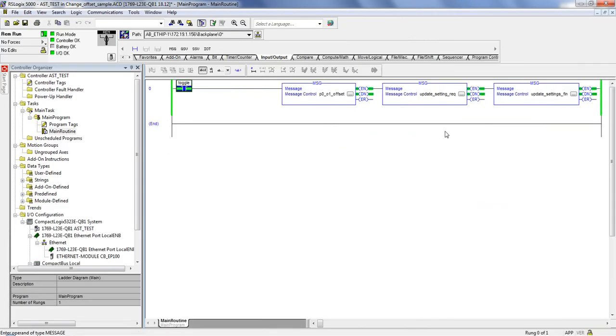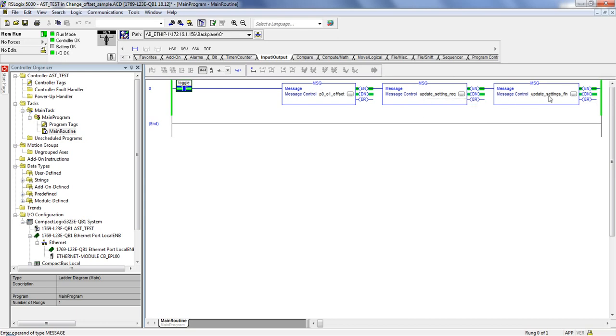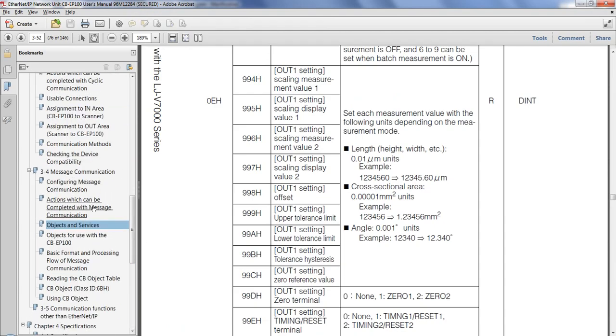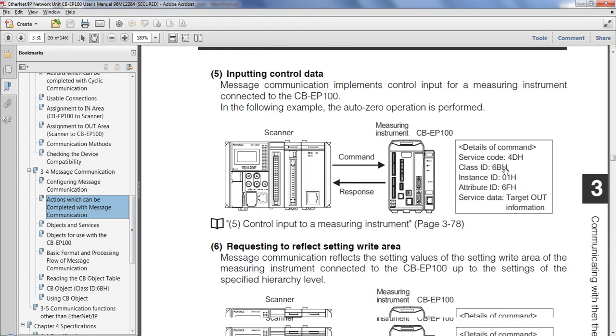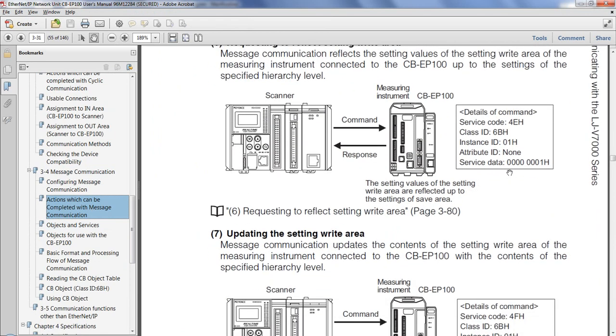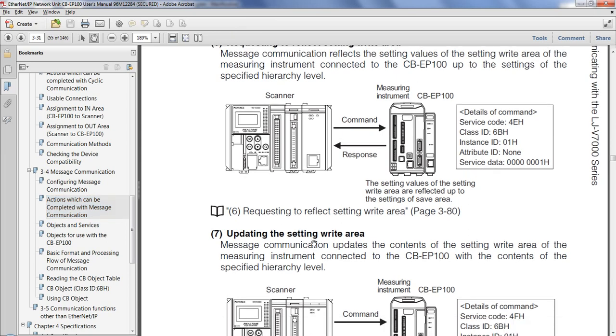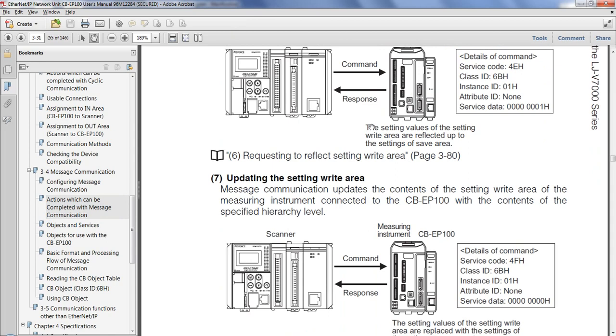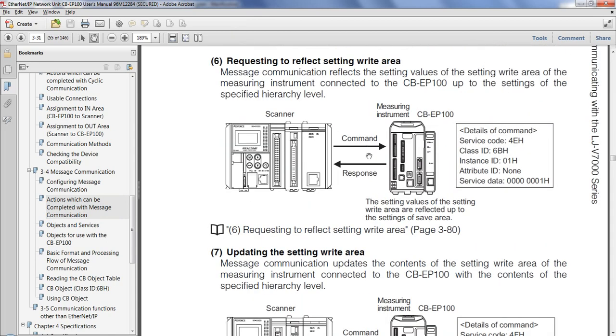One thing I actually forgot to go over earlier was these two messages over here. So this one is my message for changing the offset value. One thing when changing data on the unit, you need to send two more requests after it. One of them is going to be to request that the data be updated. And then another one to actually update the data. Both of these, again, are laid out directly in the manual. So very easy to find. The customer would simply need to copy these two commands right here. We're requesting to reflect setting write area and updating the setting write area. So, again, customer would simply need to make whatever changes they want to make. And then at the very end, go ahead and send these two commands to make sure all that data is now updated on the controller.